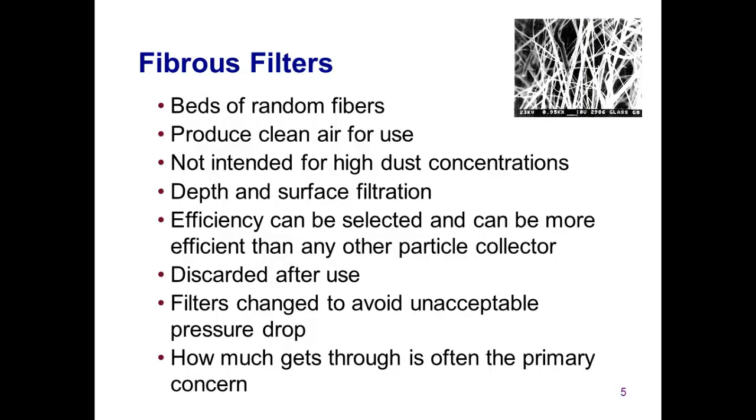As mentioned before, fibrous filters are beds of randomly oriented fibers that generally are used to produce clean air for use. These filters can be manufactured from many different fiber materials. They are not intended for high dust concentrations because they cannot be cleaned. So, to permit long periods of use, fibrous filters are generally used with lower concentration dusts. These filters collect particles both on the filter surface and within the depth of the filter, but the depth is more important to overall efficiency.